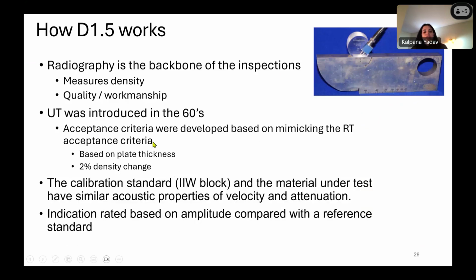This is not how it works, because the material you are going to use on the field is going to be different from the material you are using as a reference standard block, because there are different processes to manufacture those steels, and those manufacturing processes affect ultrasonic velocity. The way you produce those steels is how their ultrasonic velocity is going to be affected.